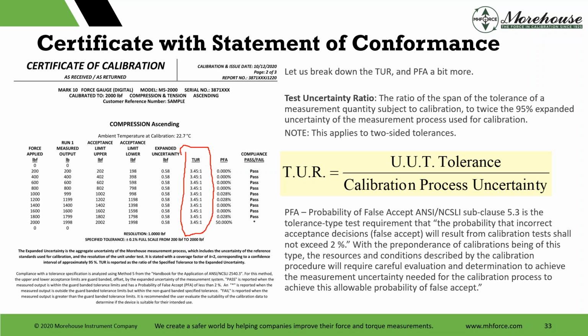And then we have what's called the PFA, which is the probability of false accept. The probability of false accept is defined in ANSI Z540.3 as a tolerance type test requirement that the probability that an incorrect acceptance decision, false accept, will result from a calibration test shall not exceed 2%. With the preponderance of calibration being of this type, the resources and conditions described by the calibration procedure will require careful evaluation and determination to achieve the measurement uncertainty needed for the calibration process to achieve this allowable probability of false accept.